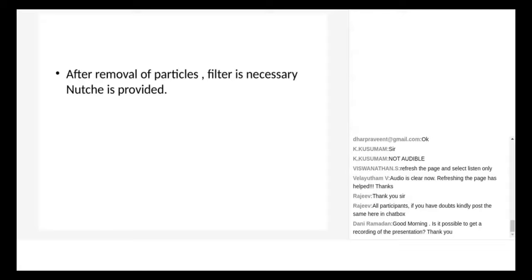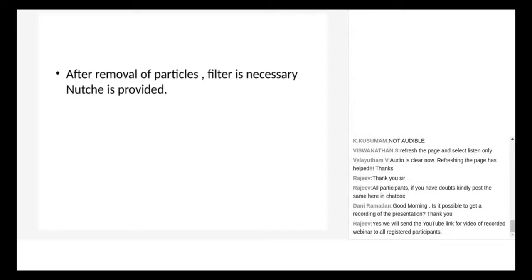Because water becomes hot over reuse, at about 90 degrees centigrade, you take it on the polyester cloth filter and allow it to stay there since there's no hurry of filtration. The entire cake gets drained of water, and then you take out the cake as ash and dispose it off with coal ash, which normally separates below the grid on which the fuel is fired. So you've disposed of ash completely and reused water - hardly 200-300 liters per day makeup would be necessary in this main tank. That is all that is needed for this scrubber.